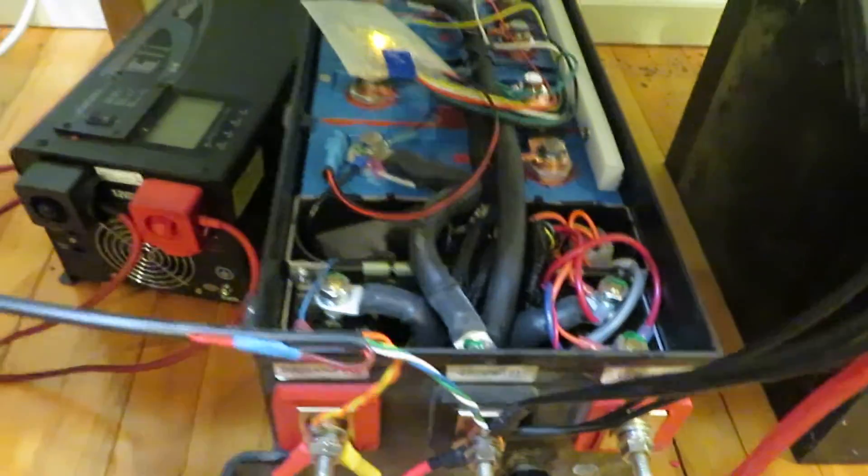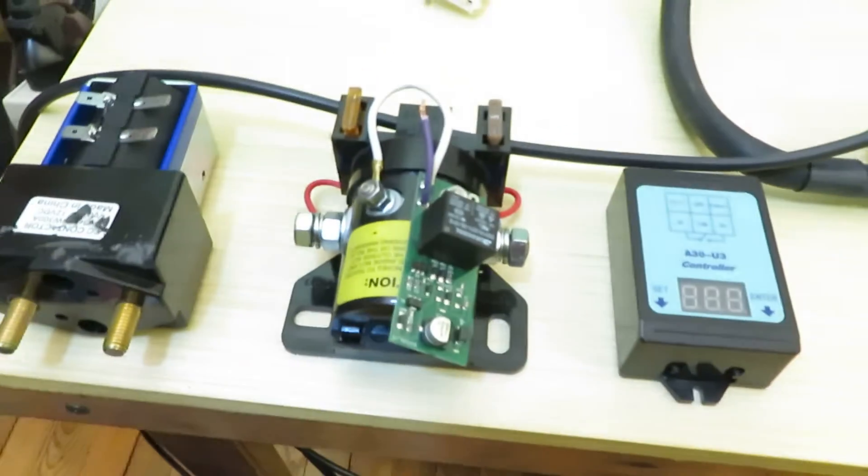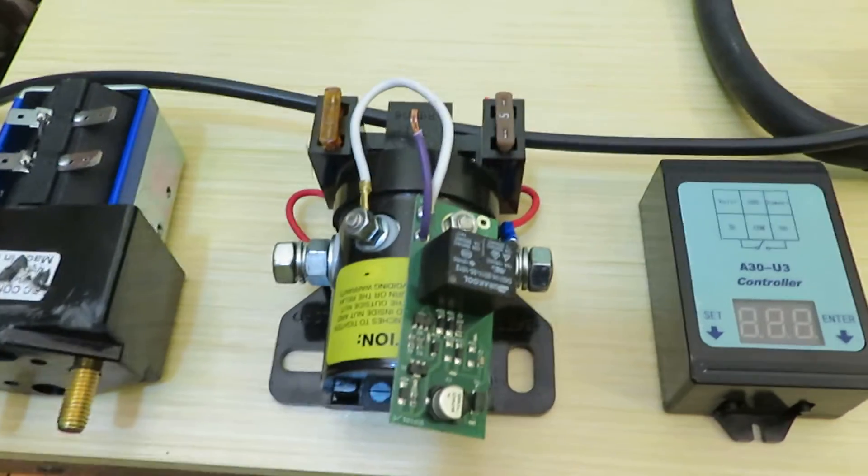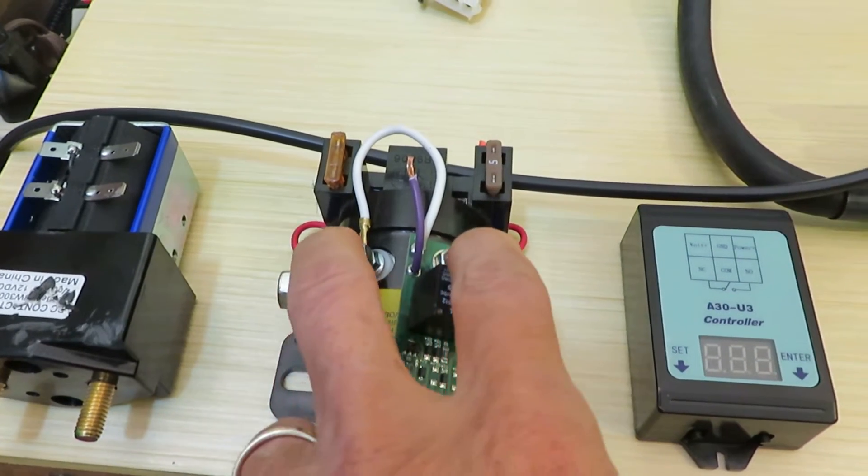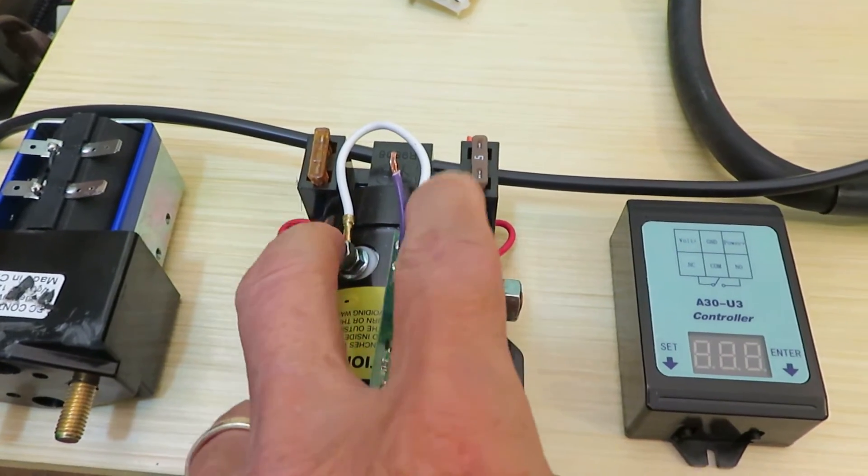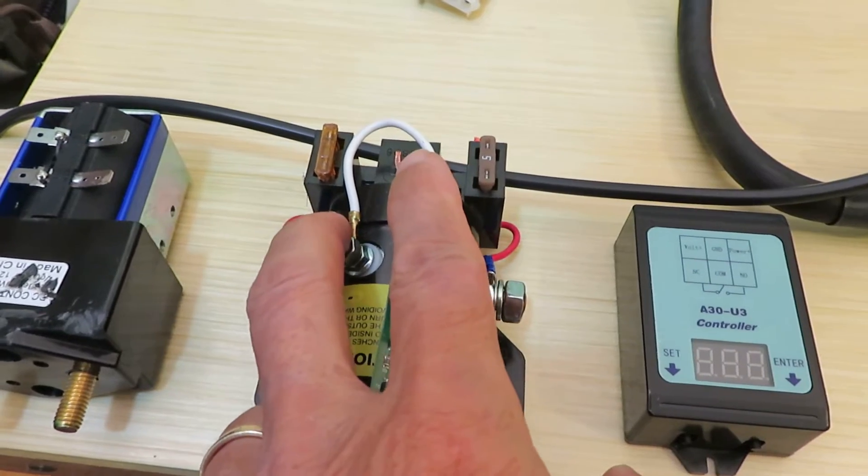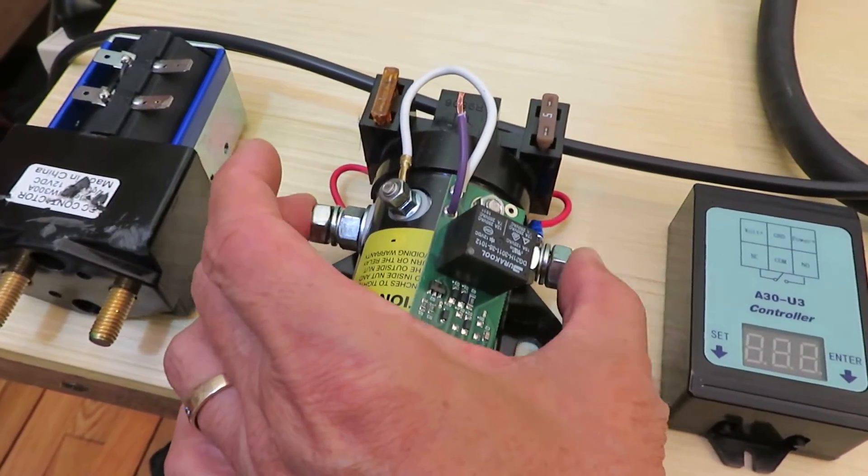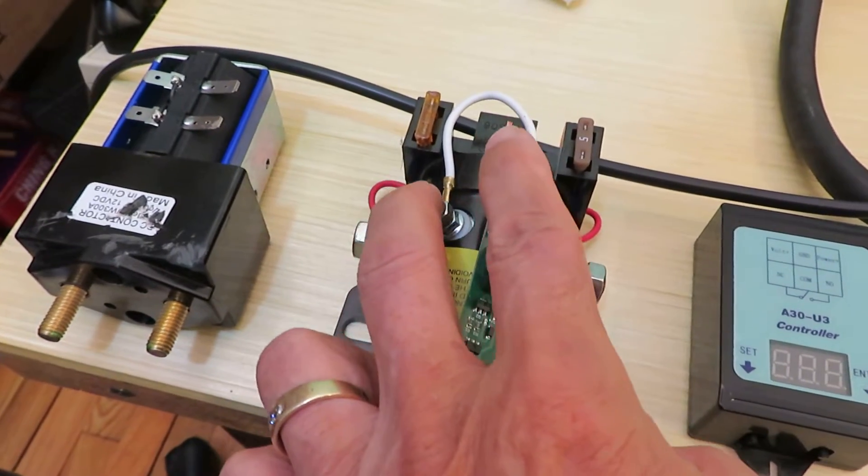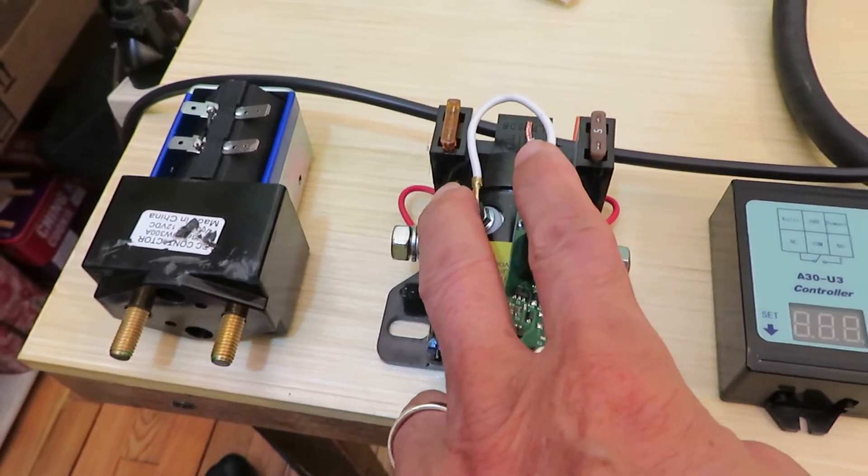The second one is a latching relay. The reason is latching because you don't need a constant power source to close it. You pulse it will latch. You pulse it again it will unlatch. So this way on and off depends on how many times you pulse this.